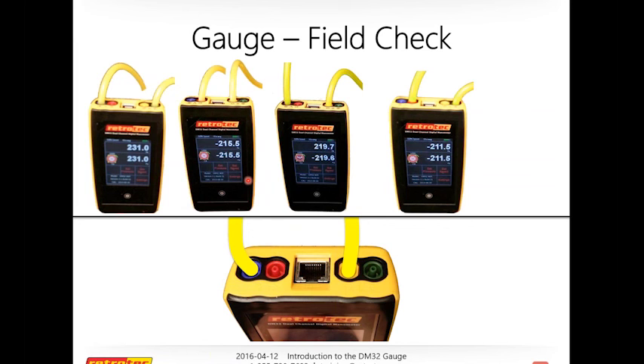The point being, we've set both channel A and channel B to read Pascals, so pressure, and when I insert the tube onto the port at the top, it will create a pressure inside of the tube. And because these two channels, as I explained earlier, are two separate manometers connected only by a common battery, they should both read the same pressure within about 2%. So when I plug this one in and create a pressure, and this tube is connected to this tube, the pressure in this tube is going to be reported with a difference to the inside, and so will this. So they should be the same.